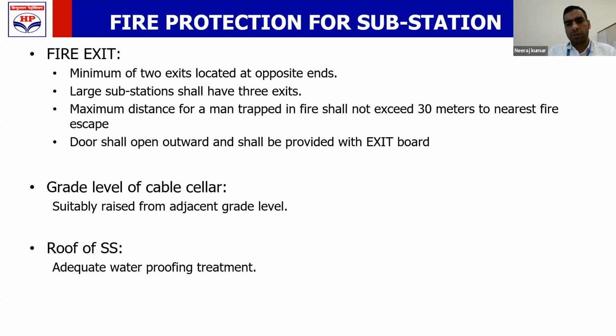Now, how will we decide how many exits are enough? For that, you should consider a man trapped in the fire. Assume that there is a fire in the substation and a person is trapped in it. If that person walks through all your panels and all your VFDs, the actual traveling distance to the nearest exit should not be more than 30 meters. This is how you decide how many exits should be provided, with a minimum requirement of 2. So your substation may be some 120 meters long, and you may end up finding that you need 4 exits. So the ultimate criterion is a man trapped in the fire inside the substation. For him, the traveling distance to the exit should not be more than 30 meters.